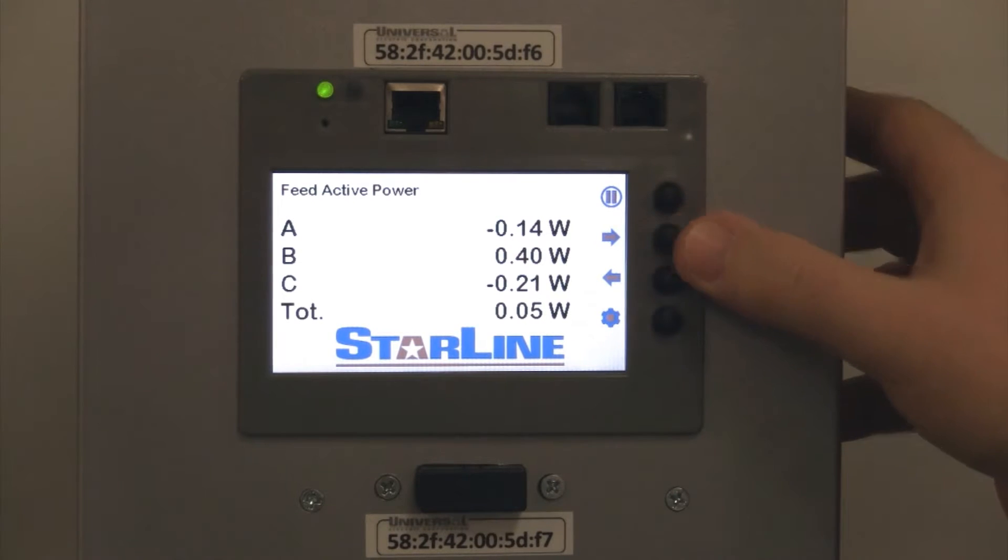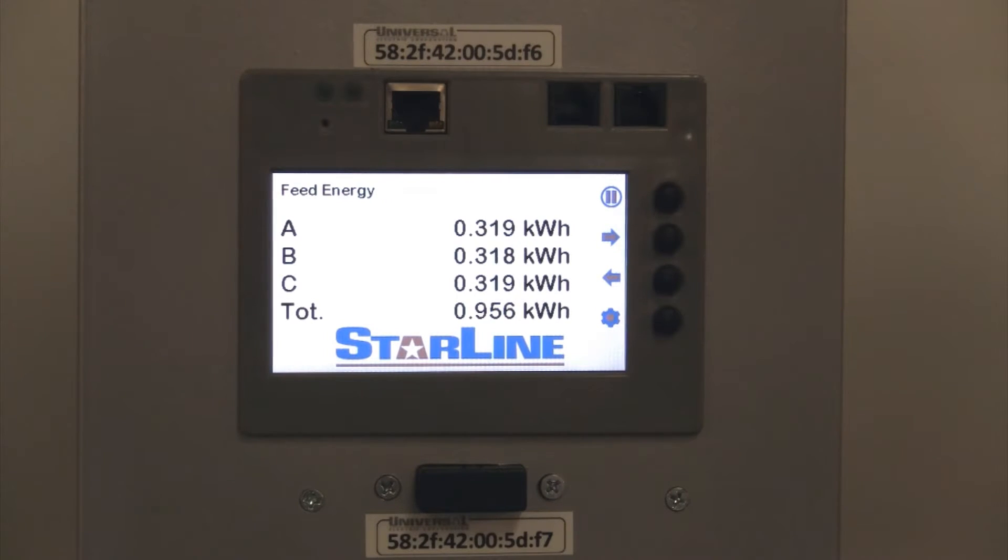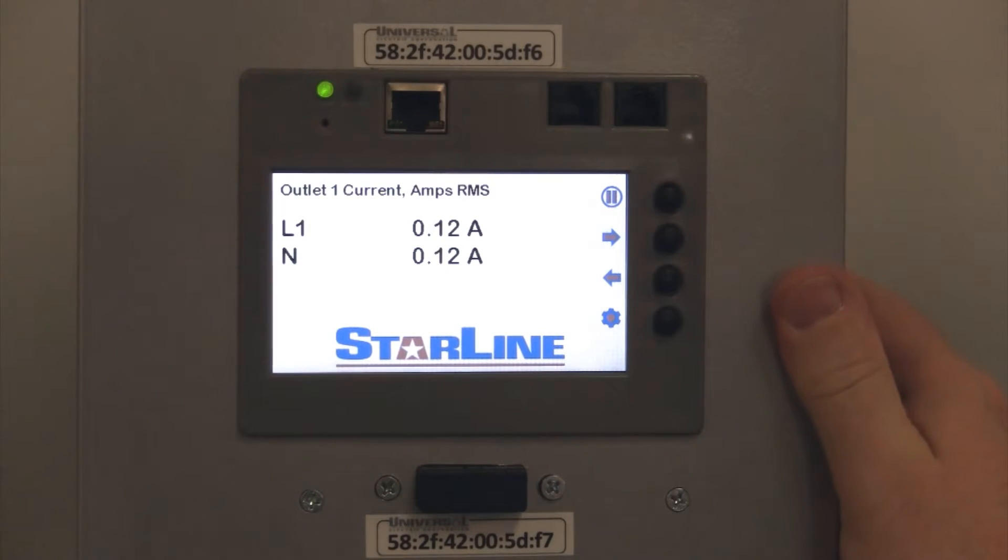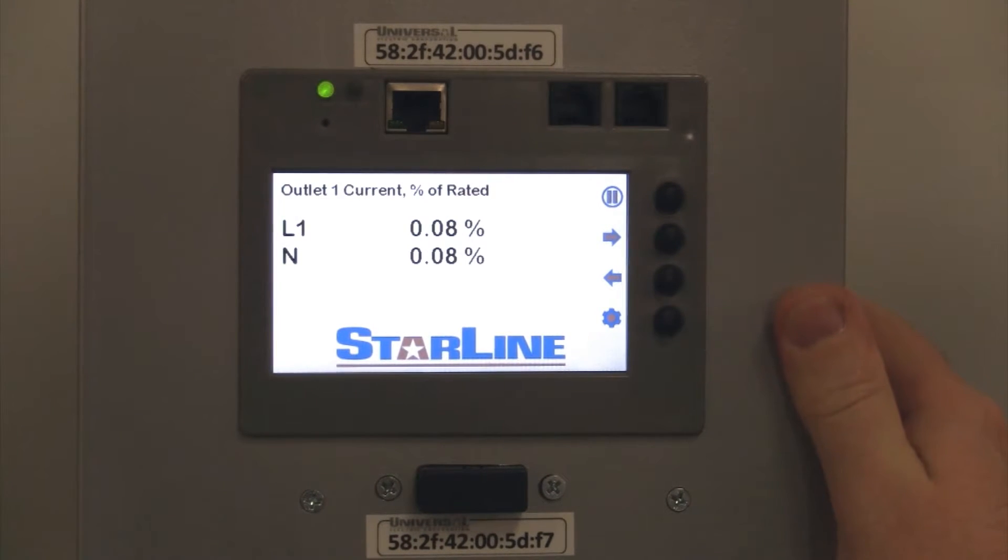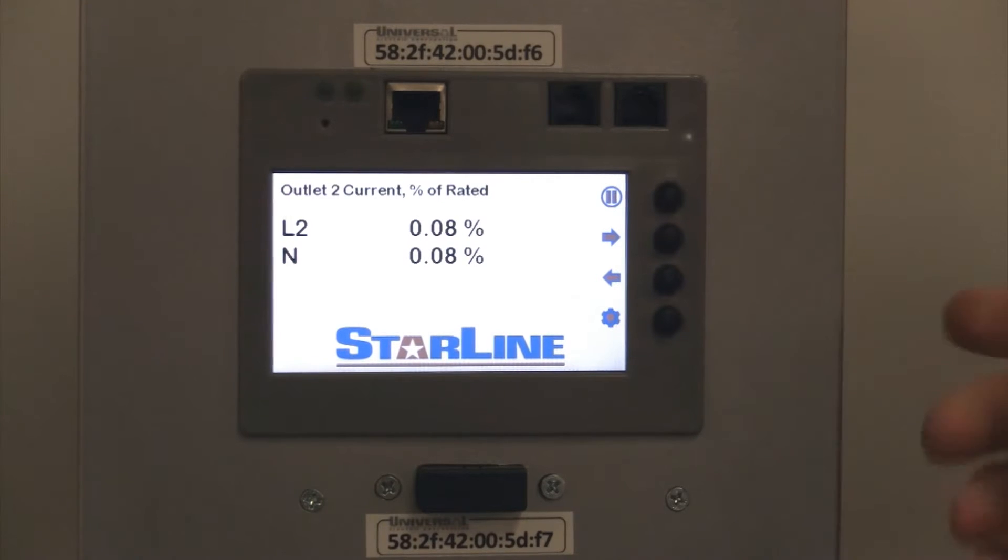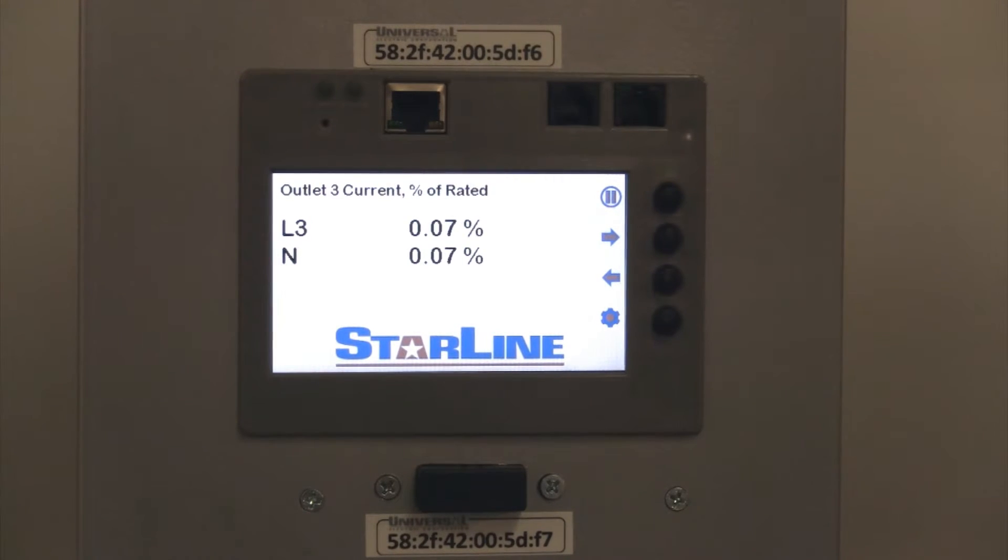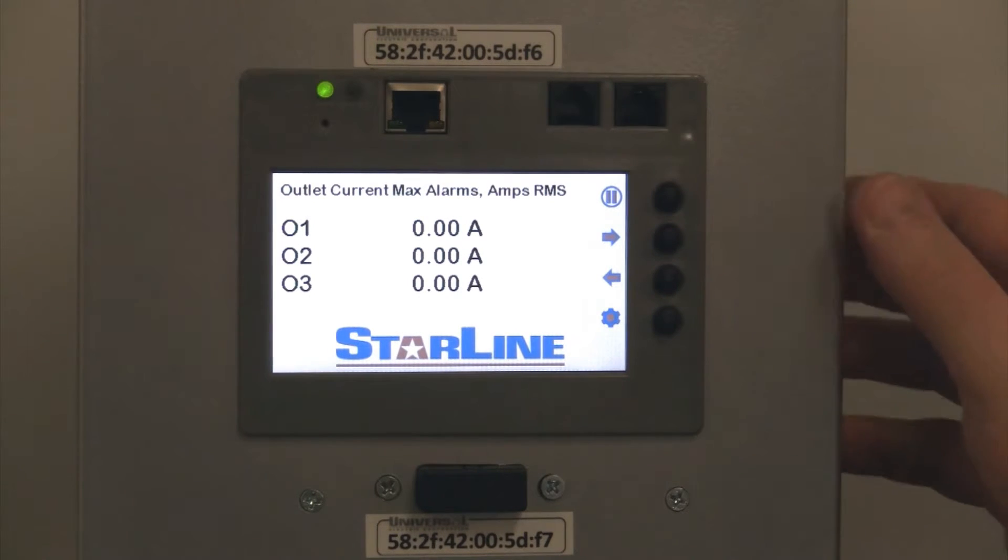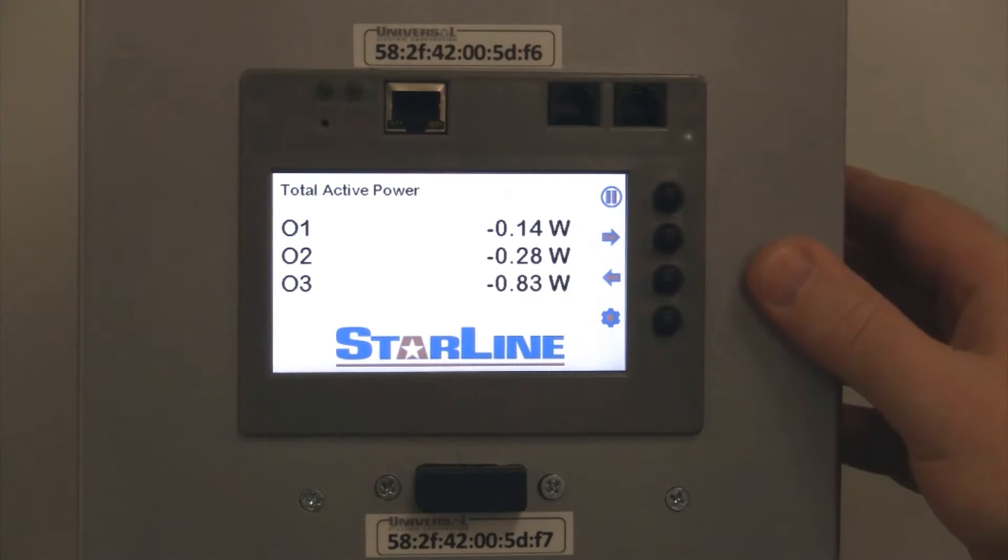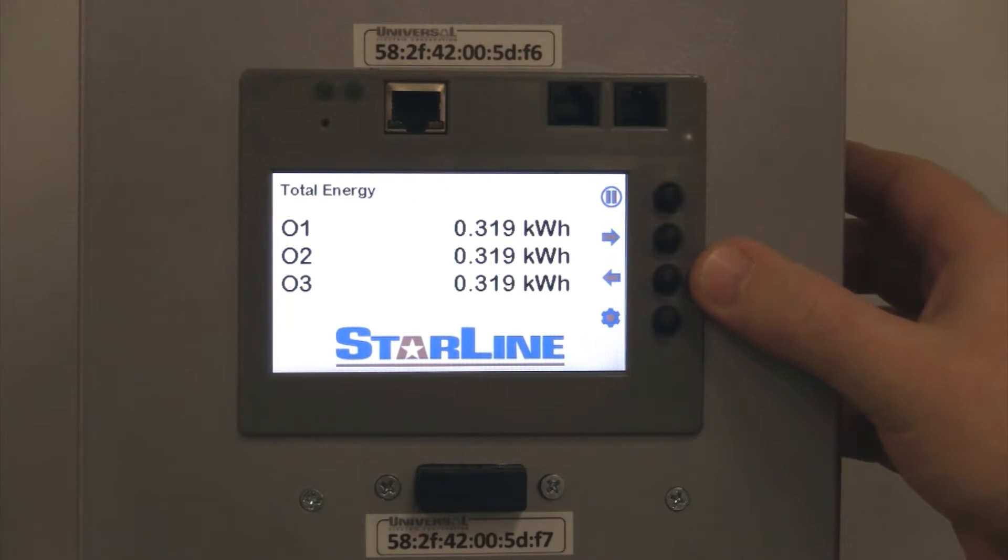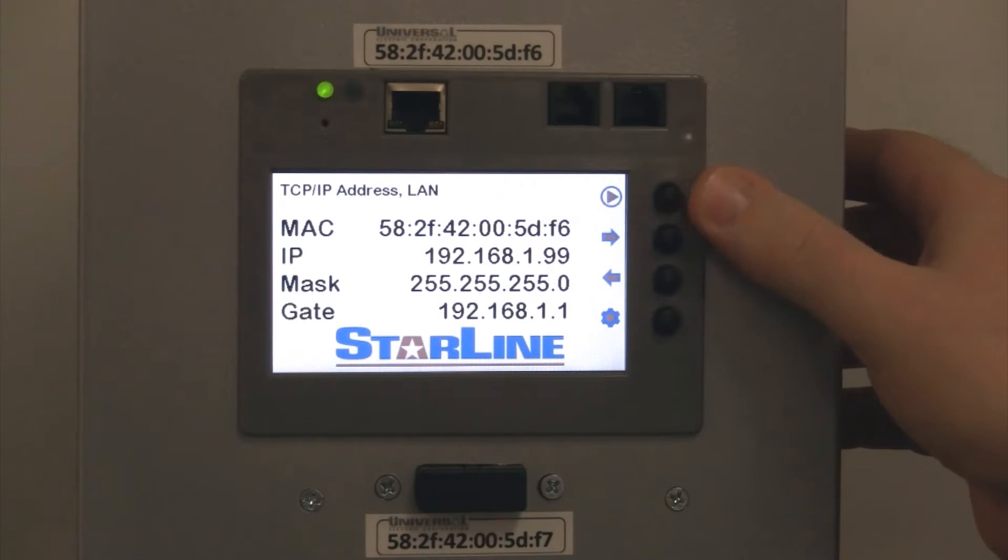This is a true power monitor capable of taking in six current inputs, calculates kilowatt hour usage, and is revenue grade accurate to greater than 99%. You have your line-to-line readings, line-to-neutral options, voltage, apparent power, reactive power, and the like. So anything that you would need to see from an energy perspective, you would be able to see.